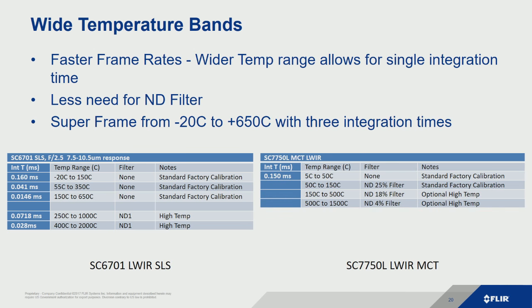Is this the same for all long-wave detectors? Not necessarily. Long-wave MCT — FLIR uses some in our cameras — and with a particular readout long-wave MCT has very short temperature ranges: 5 to 50°C, 50 to 150°C, and so on. The SLS has a clear distinct advantage here. So even if you're working in the long-wave, the detector material and the readout combination are both necessary to help you get the best performance.